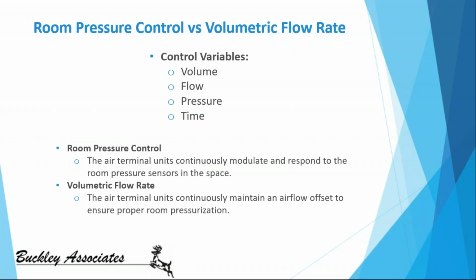So really there are two methods of control, as I just mentioned. They're either going to be room pressure control or volumetric flow rate. When we look at control variables inside of a space, we need to pay attention pretty much to 4 different variables. Those variables are volume, flow, pressure, and time. However, the most commonly used variables that we're going to look at here are the volume and the pressure. The other two, even though they are still considered variables in these spaces, are almost always associated with the other 2 variables. Let me further explain.